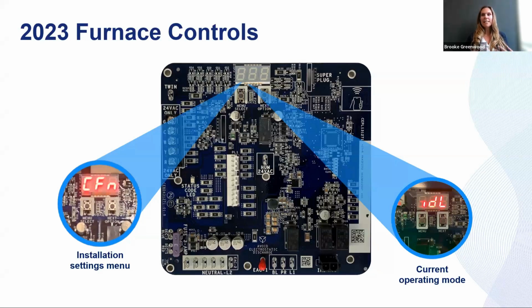One of the improvements with the new Comfort line coming out is that we're actually going to house the last 7 fault codes in the control board. Today, you're getting the most recent severe fault that's flashing in that LED, and when you take the door off and lose power, that goes away. These 7 faults will be housed in the memory, and you'll be able to pull them off into the app as well.